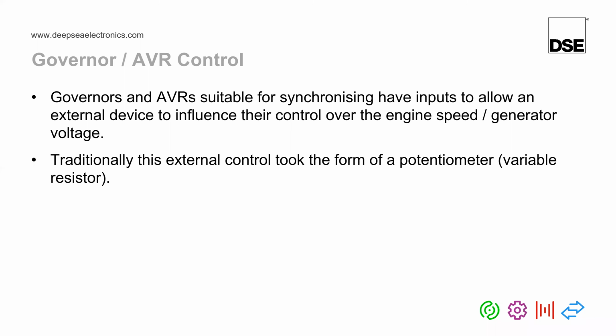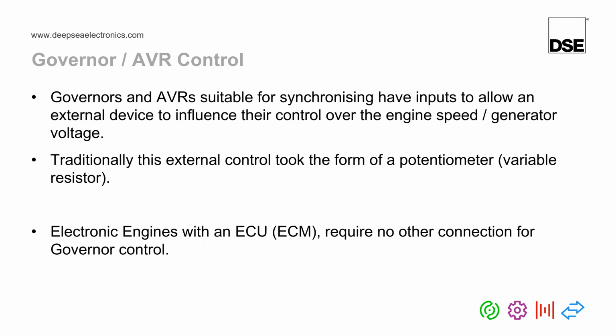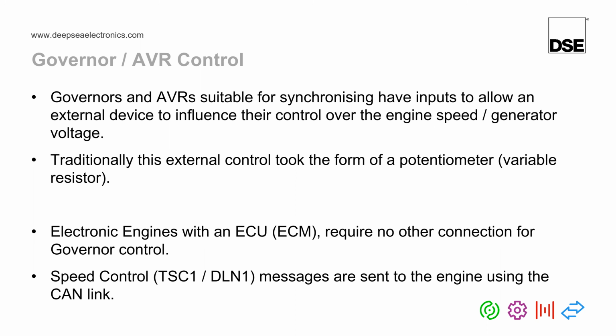However, when we talk about electronic engines, such as ones with ECUs, normally these don't have an input for a variable resistor or something similar. But that's not normally a problem, because with most electronic engines, we'll be using CAN bus messages to do the speed control. And those CAN bus messages are normally in the form of something called the TSC1 or DLN1 message. Now, for the sake of this presentation, we're going to be assuming that in most cases, we're going to be wiring into a governor's or AVR's remote bias input, effectively the input on the governor or AVR that uses a potentiometer or a variable resistor. But the principles I'm going to discuss through this presentation are exactly the same if you're using the hardwired signal or a CAN bus signal.